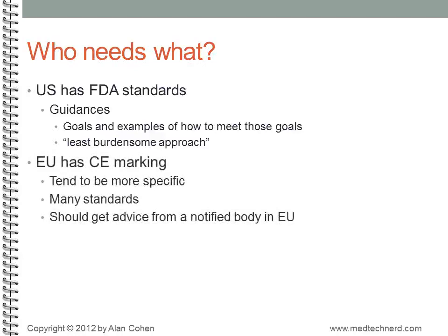The EU clears medical products for sale through the CE marking system, which certifies conformance to the EU Medical Devices Directive. Compared to the US process, obtaining a CE mark tends to be a more tightly specified process for the types of devices that we're focusing on in this presentation. There are a fair number of applicable standards, and these tend to be more specific than their corresponding FDA guidances.